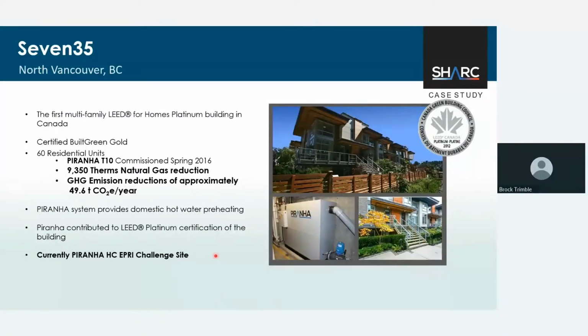So the first project that we're going to see is called 735, located up in North Vancouver, BC, in Canada. This is a 60 unit multifamily project. It is stacked townhomes and condominiums. In this site, all of the sanitary wastewater discharge is collected in a small tank just at the edge of the property. We use one of our Piranha T10 units that you can see down here, capturing all of that wastewater energy, recovering it, and the Piranha puts out the domestic hot water that we use, using that recovered energy directly into the hot water tanks right here that you can see beside the unit. So this is installed directly in a mechanical room.